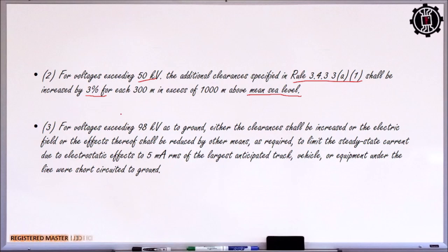30 cm. So, dalagdagan mo ng 30 cm yung measurement mo, yung clearance mo for every 300 meters na excess. No? For voltages exceeding 98 kilovolts AC to ground, either the clearance shall be increased or the electric field or the effects thereof shall be reduced by other means. No? So this is if sobrang taas na ng voltage, 98 kilovolts, no? Phase to ground. So either ang gagamitin natin is yung ating conductor is may cover na, that is to decrease no the field effect, no, the electric field effect, or tataasan talaga natin yung ating clearance.